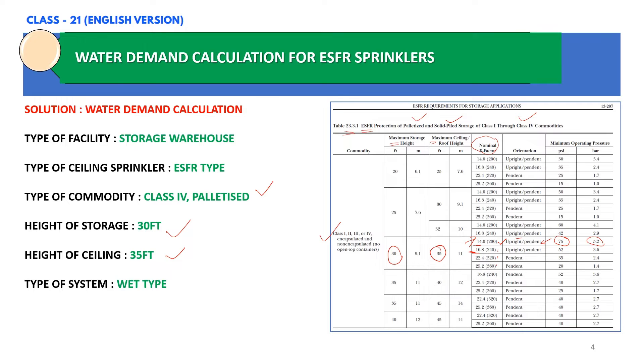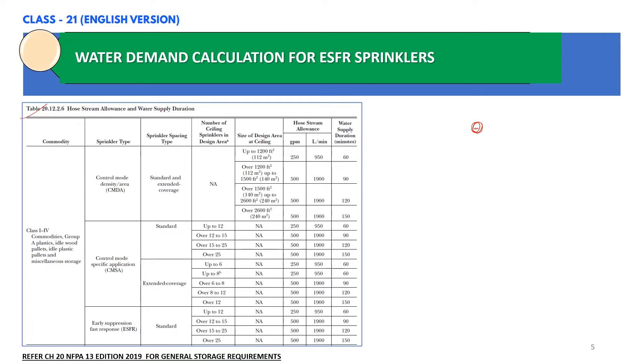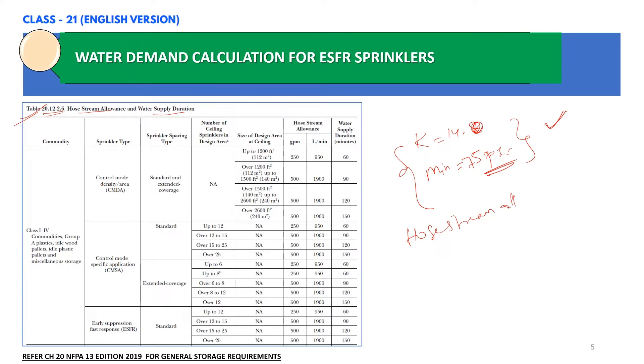Now we move to the next slide to calculate the water demand requirements. On screen is Table 20.12.2.6 — Hose Stream Allowance and Water Supply Duration. From the previous slide we identified K factor 14.8 and minimum operating pressure of 75 PSI. Here we consider hose stream allowance and water supply duration. Our case is Class 4, so this table applies. We are not considering CMSA or CMDA — we are considering ESFR sprinklers. The design area of sprinklers selected is 12.